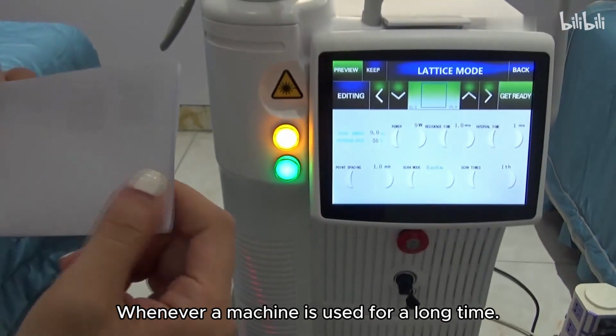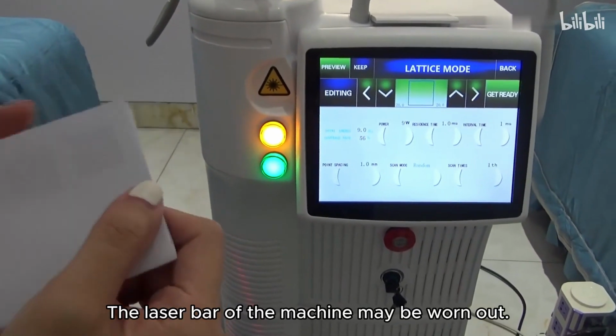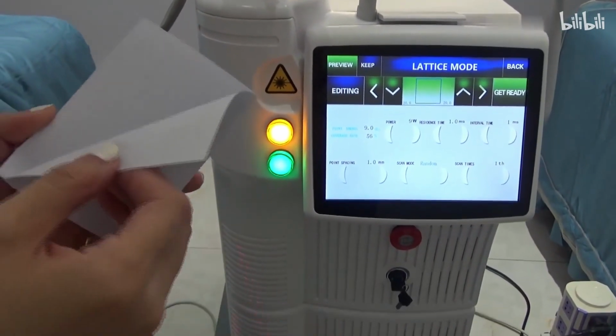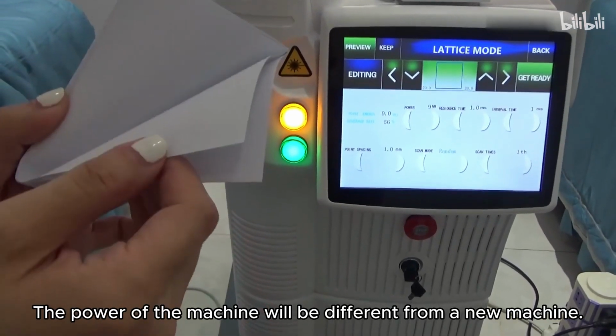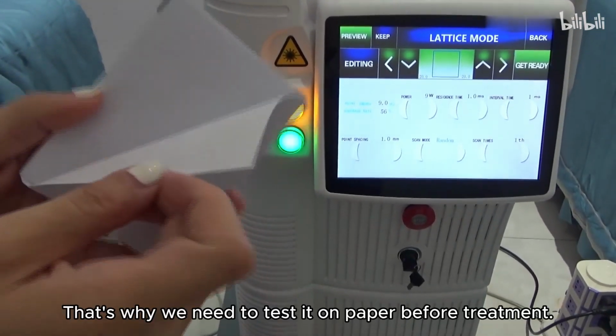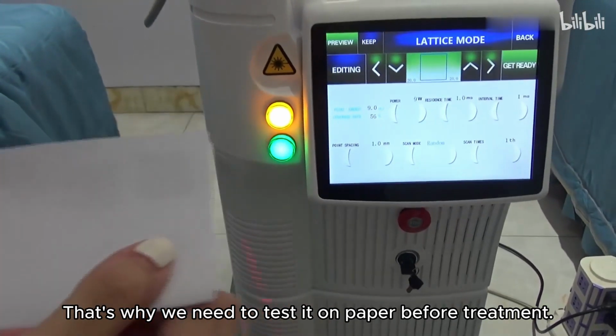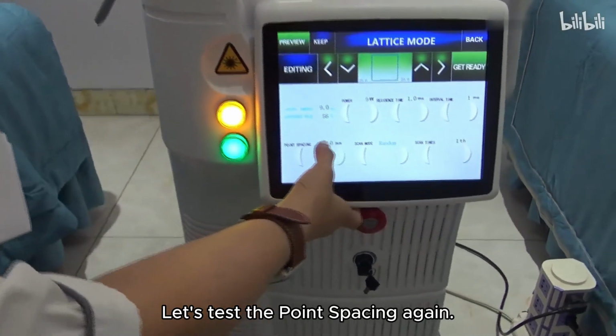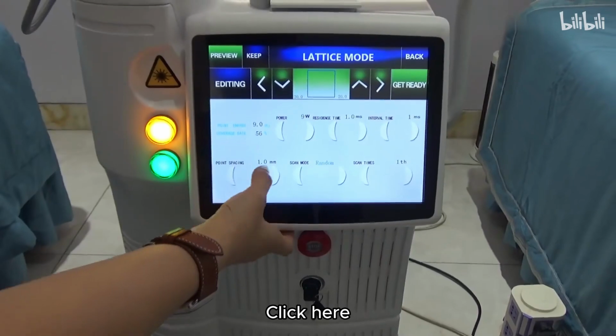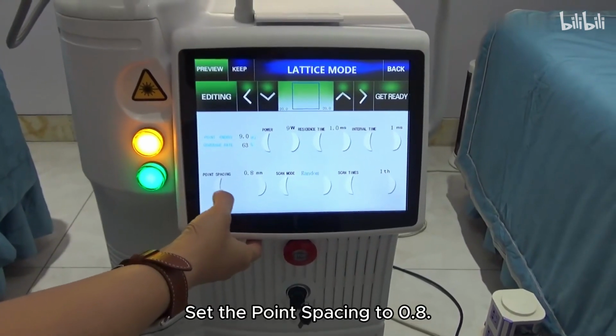Whenever a machine is used for a long time, the laser bar of the machine may be worn out. The power of the machine will be different from a new machine. That's why we need to test it on paper before treatment. Let's test the point spacing again. Click here. Set the point spacing to 0.8.